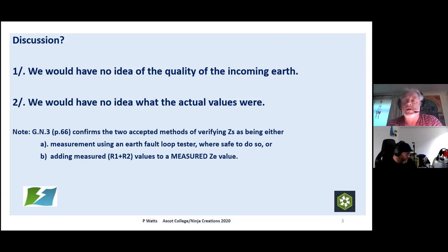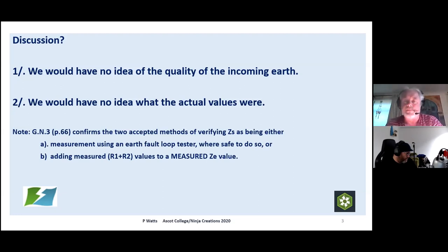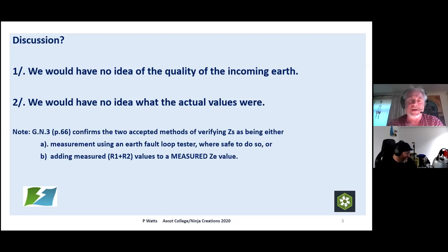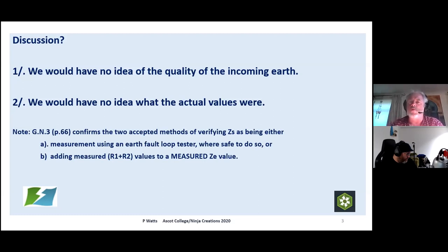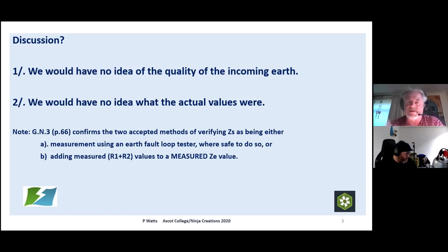At no point are we testing the integrity of the earth at all. Pure bovine excrement. We'd have no idea of the quality of the incoming earth, and no idea what the actual values were. Guidance note 3, page 66, says the two accepted methods of verifying Zs are: measurement using an earth fault loop tester when it's safe to do so — and let's face it, if you've got socket outlets, when isn't it safe just to plug it in? It's just like plugging in a kettle or a toaster.